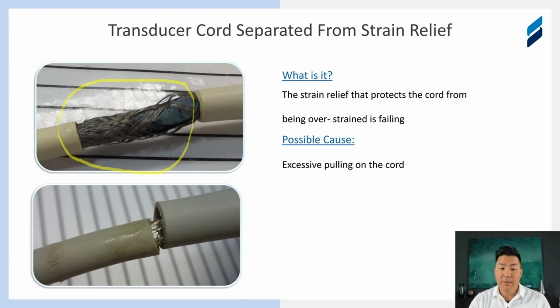But if you see this, remove it from service immediately, because this can be a very simple and straightforward repair, and over the course of a day or two can turn into something of a mess because the wires and the grounding are all exposed, and now it's extraordinarily vulnerable to other damage. So we highly recommend if you see this, if your sonographer sees this, get this out of service as quickly as possible so it can get rectified, and a very inexpensive and quick repair will avoid possibly a catastrophic failure in the future for you.